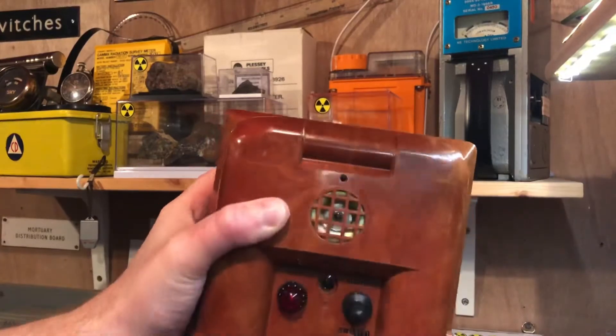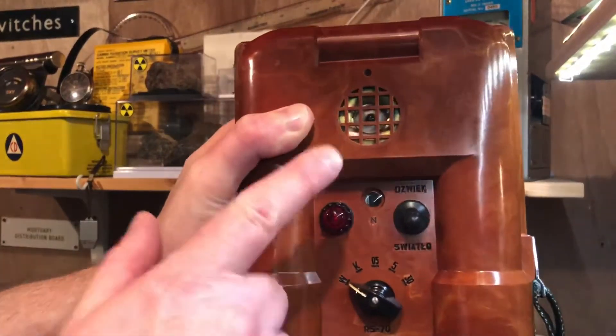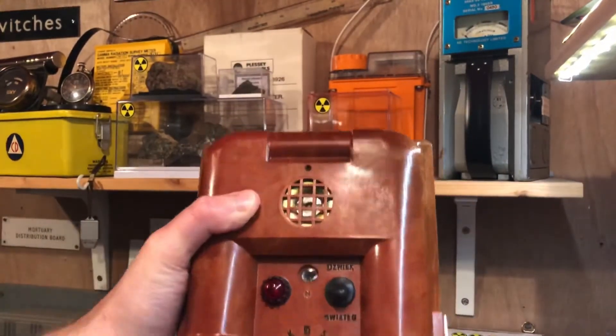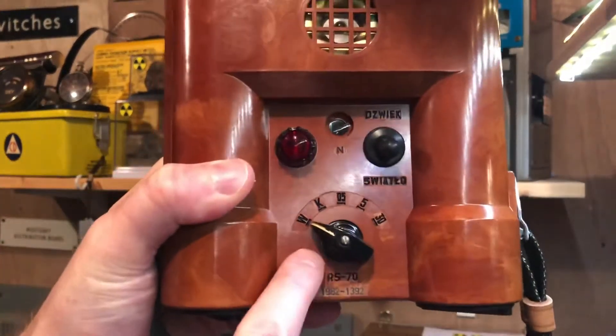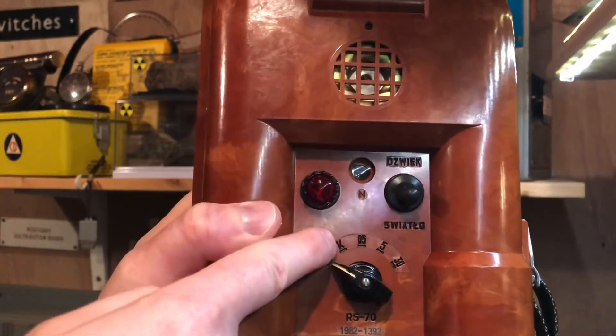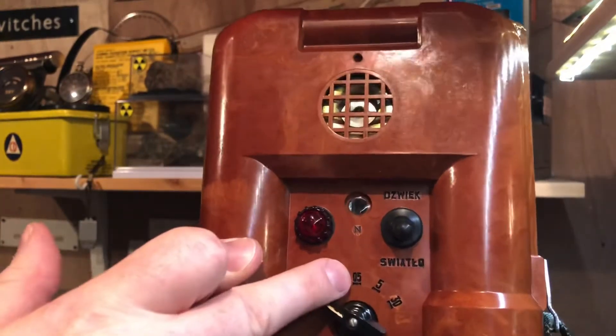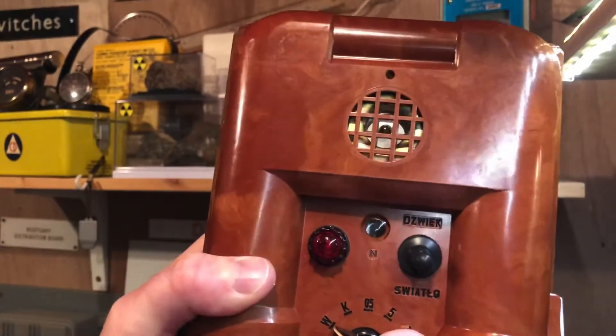It's quite different as a meter in that it doesn't have a display. It really only has a light and a buzzer from the speaker here. It's set to warn you at different intervals, and they're quite high. The switch positions are: W is off, K is test, and then we have 0.5, 5, and 30 — measuring Roentgen. So we have 0.5 Roentgen, 5 Roentgen, and 30 Roentgen.